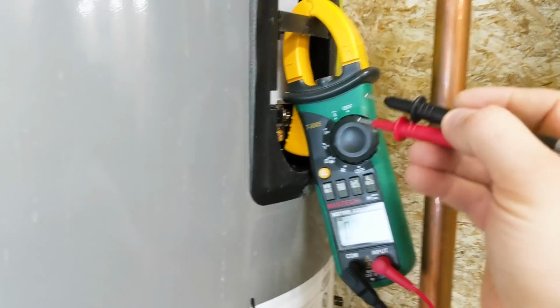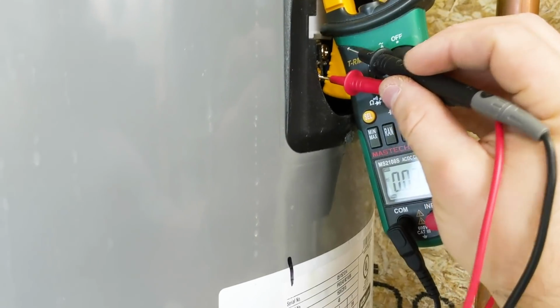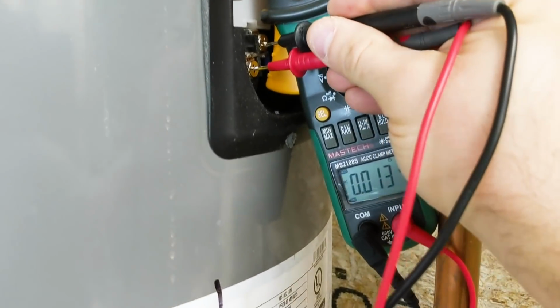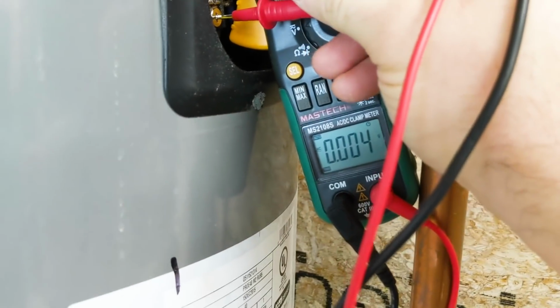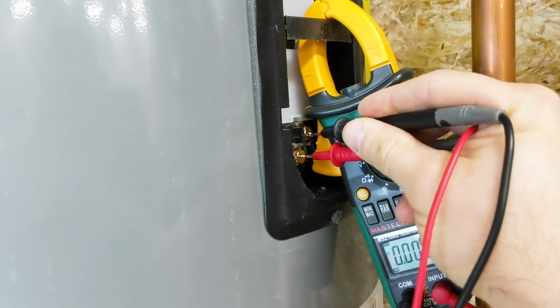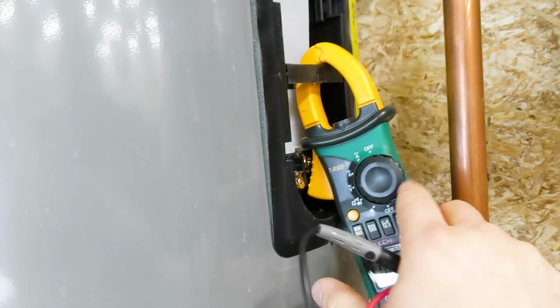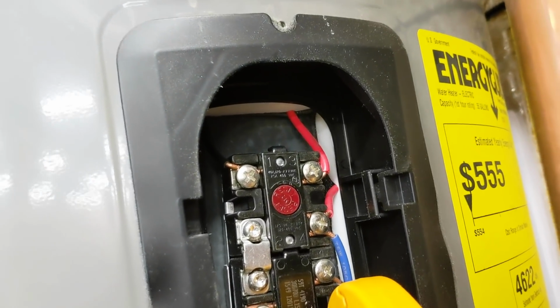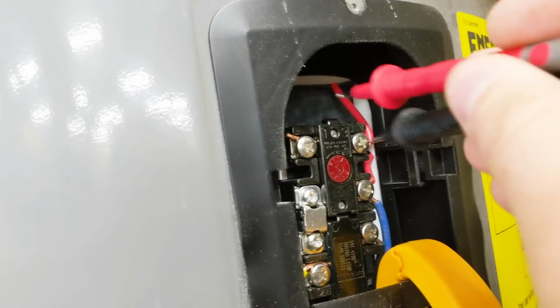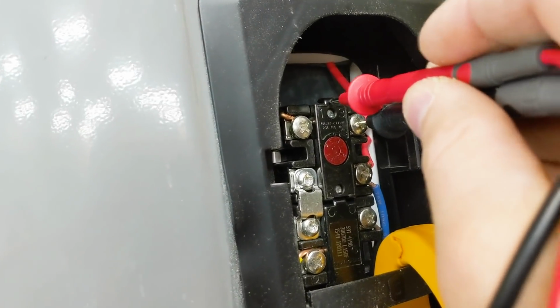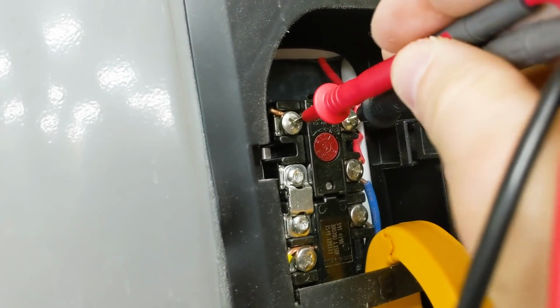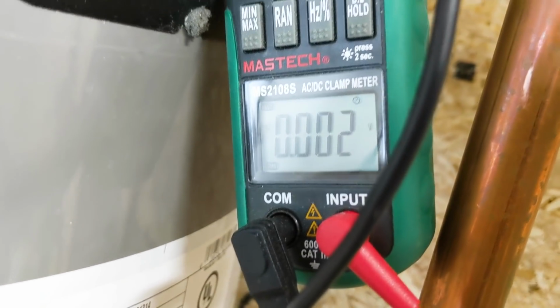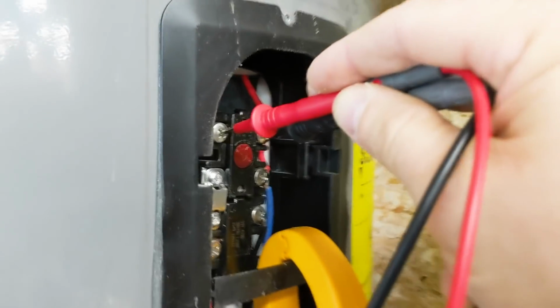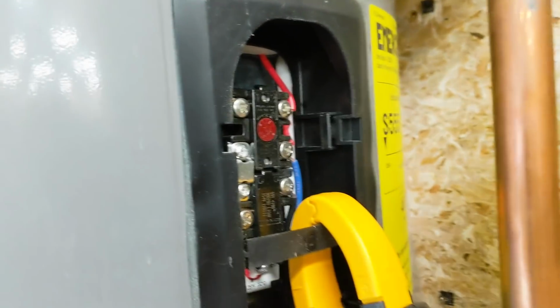With a multimeter, let's verify we don't have any power out here. Even though we know the circuit breaker's off, we always want to verify we don't have any voltage at this point. Now let's take off the plastic cover and check at the thermostat leads. So there's a red and black wire right at the very, very top, and that is going to be our two hot legs. So we're going to check right there. And no voltage. So we successfully turned off the circuit breaker, so there's no power out here.